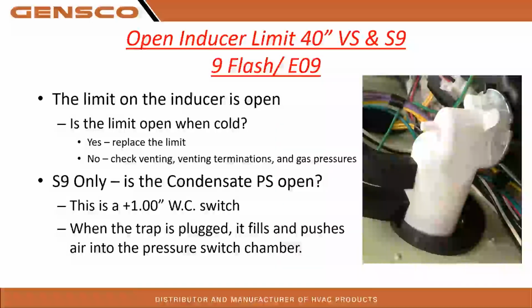All right. The number one code that's called into tech services, other than maybe idle: the 40-inch and the S9, right? So we have inducer limit, right? We have a limit open on the inducer motor when it's cold, right? So if yes, replace the limit. If no, check venting, terminations, and gas pressures, right? So this would be more of the 40-inch furnace, this top one here.